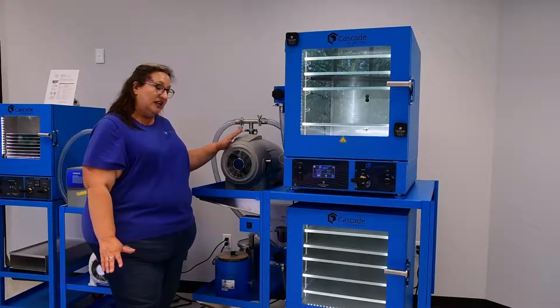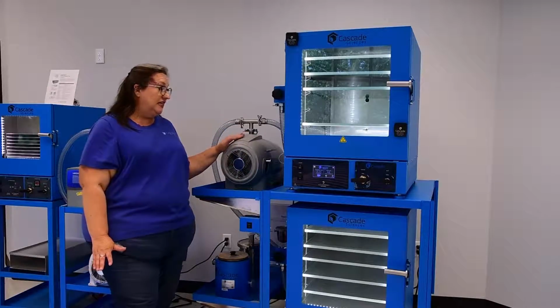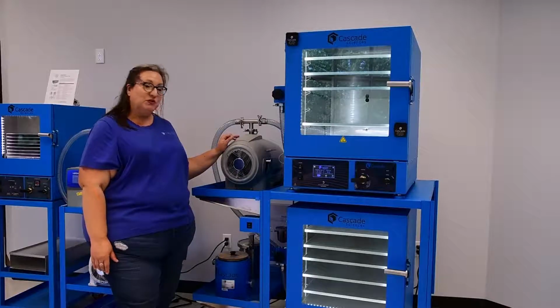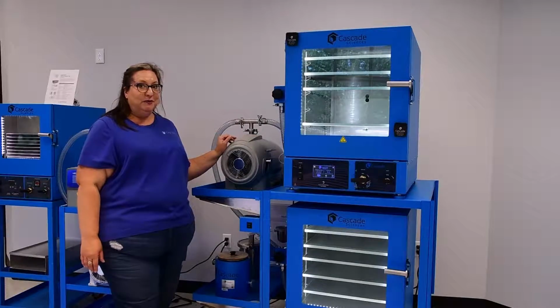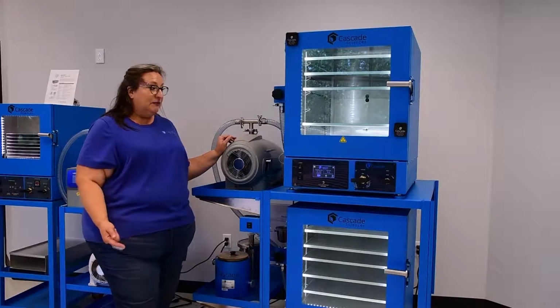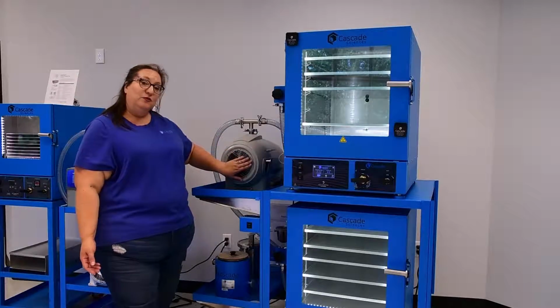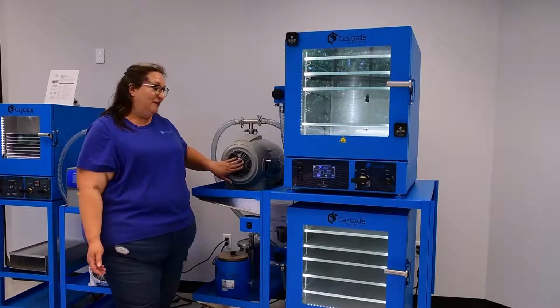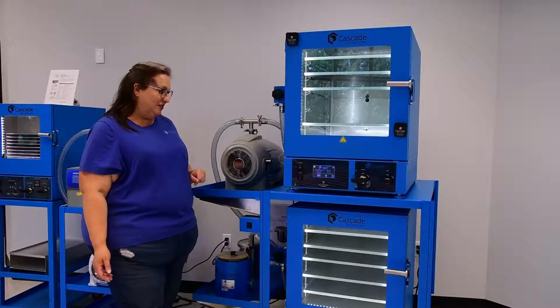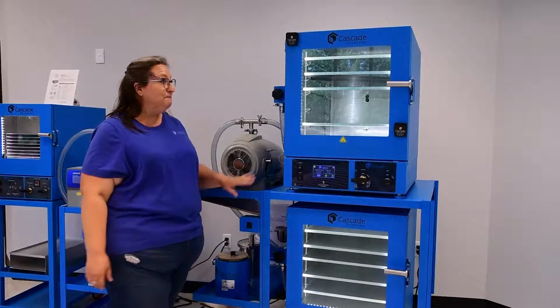This system features an Agilent IDP 15 9 CFM dry scroll pump. I'm not going to put an oil pump in your lab. They're dirty, they're messy, and when CGMP comes, watch out. If you've got a rotary vane pump, it's going to cause you some trouble in terms of compliance.